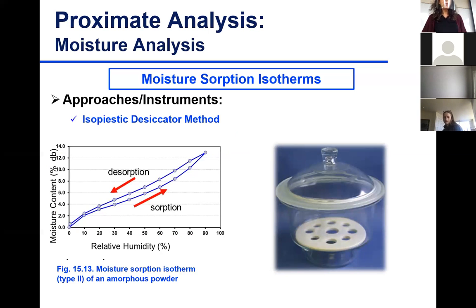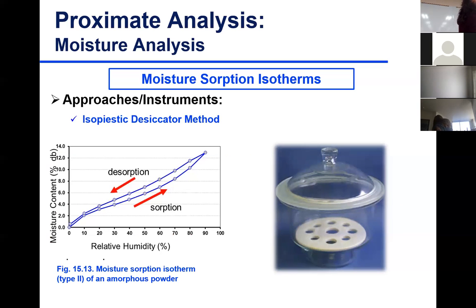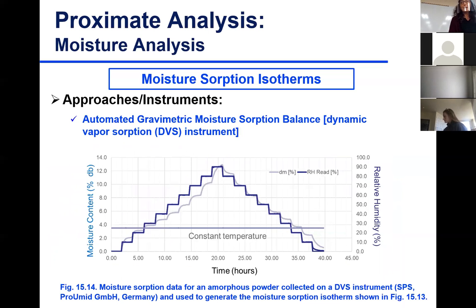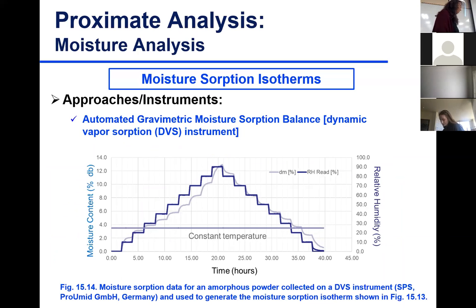You can plot both sorption and desorption isotherms. There are also dynamic vapor sorption instruments that can give you moisture sorption isotherms in a shorter period of time, equilibrating faster and measuring moisture content and relative humidity simultaneously at different water activities — you don't have to incubate samples for two or three weeks.